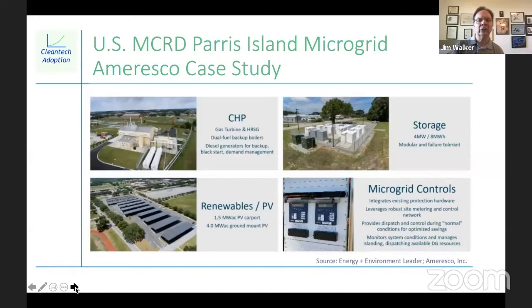So the Marine Corps wanted to upgrade with renewable energy, storage, and a microgrid controller with the most advanced energy efficiency and technology available. The concept was to produce the steam most efficiently with gas-fired generation, a gas turbine CHP device, combined heat and power, with backup diesel generators for black start capability and demand management in case of a hurricane, since Parris Island is right on the coast and gets hit by hurricanes.